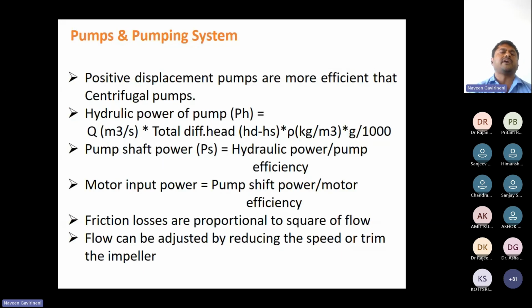Fans are over. Next, coming to pumps. Pumps play a vital role in supplying water to the system. There are two types of pumps: positive displacement and dynamic (centrifugal). Positive displacement pumps are more efficient than centrifugal pumps, but we use centrifugal pumps. Why? Because we need more flow. So that's why we are using centrifugal. This is the pump power formula: Q into delta H into density into g, divided by 1000. There are two types of this, showing how to calculate the pump shaft power, motor power, and so on.